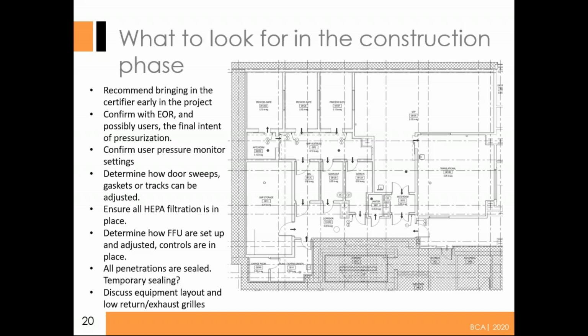Door sweeps, door gaskets, sliding door tracks. Work with the general contractor to see what type of devices they're putting in, how they're adjustable, and whether you need a manufacturer rep out there to adjust, say, a sliding door track. HEPA filtration: our fume hoods and some of our biosafety cabinets are going to have HEPA filters on them. They have a pressure drop on the system, but a lot of times they don't put the HEPA filters in until the room is clean. So coordinate with the general contractor on when the room is clean, when the filters are going to be installed, and how you're going to do balancing and pressurization, because you need those filters installed.